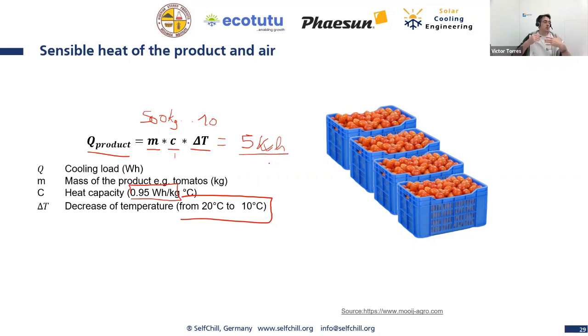5 kilowatts hour per day. If we are entering the tomatoes every day or once a week, depending on this, we will calculate the cooling load. So a very important equation, you know this well from your studies: mass times heat capacity times delta T. This is telling us the energy. How fast this energy is going to be consumed depends on the cooling curve. If the cooling curve is fast, this energy will be consumed very fast. If the cooling curve is slow, then this energy will be consumed along a longer period of time.